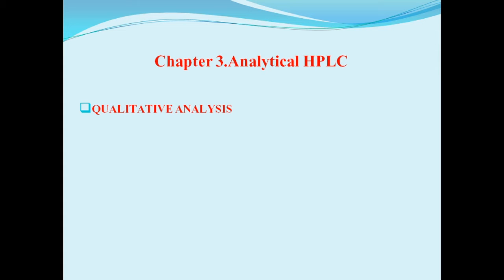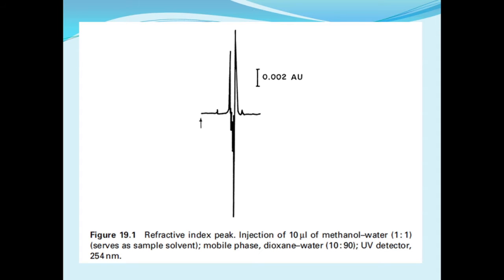Any refractive index peaks due to the sample solvent should not be confused with analyte peaks. The sample is best dissolved in the mobile phase in order to avoid being deceived by these ghost peaks. However, should this not be possible, a blind test can be carried out with the solvent used.